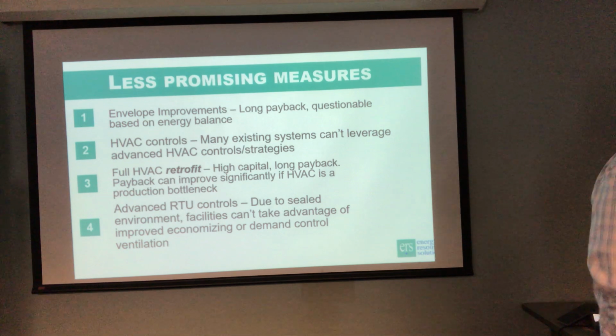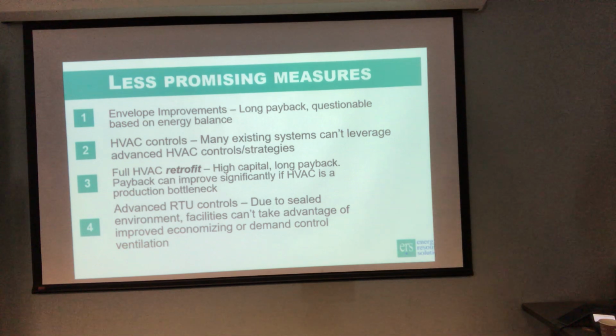I have one other question. Yeah. You mentioned high efficiency RTUs, and the idea of if you're doing a retrofit, again, using a high efficiency one. When you say a high efficiency one, do you mean including the hot gas reheat kind of system? Yep. Okay. Yep. Or even just an off-the-shelf rooftop unit with a higher SEER or IPLV value, compared to an EER 10, put in something with a 13. But even more so, if you can get units that have hot gas reheat, you're getting into a more specific sort of unit.